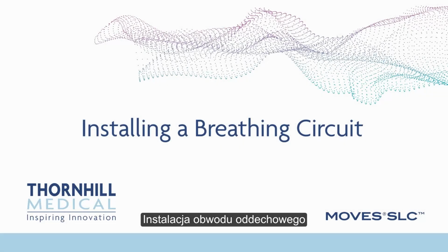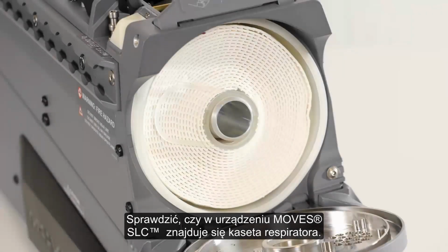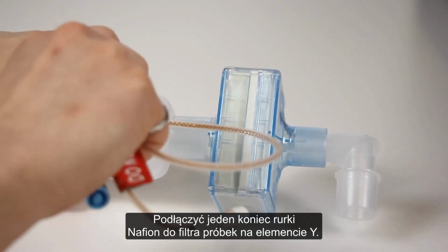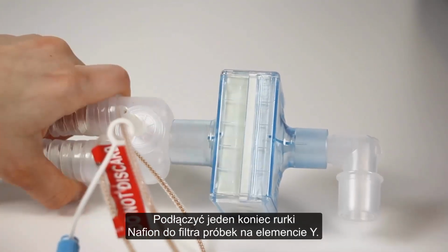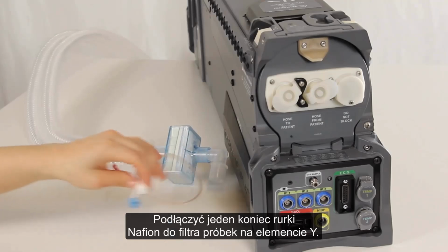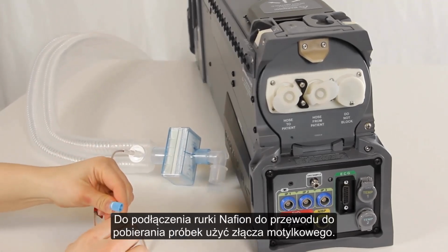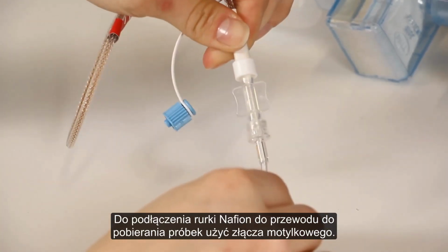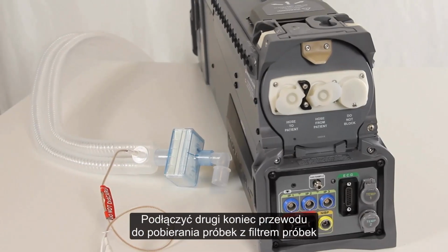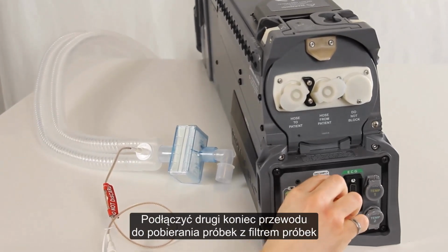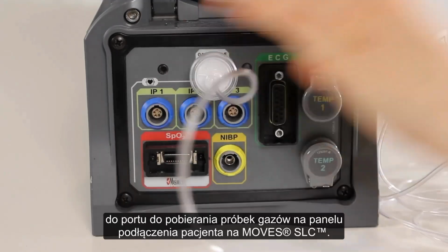Installing a breathing circuit. Ensure that the ventilator cartridge is inserted into the Moves SLC. Connect one end of a Nafion tube to a sample filter on the Y-piece. Use the butterfly luer connector to connect the Nafion tube to the sampling line.